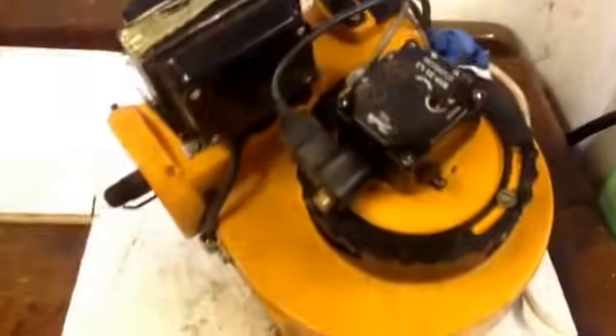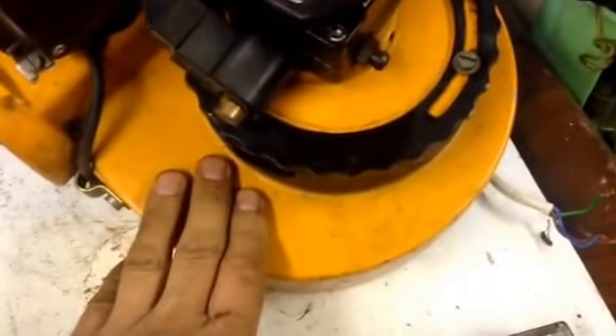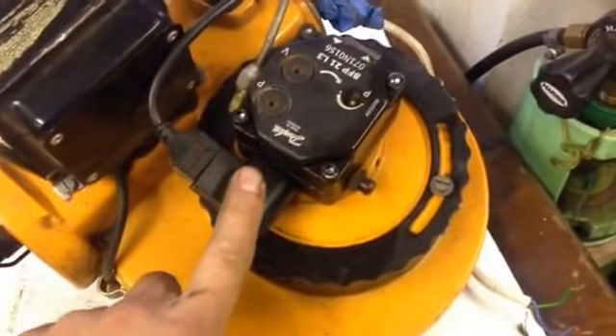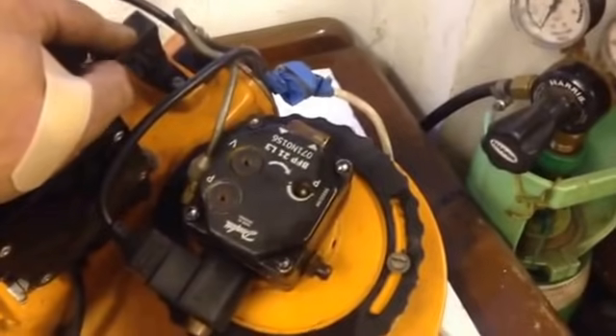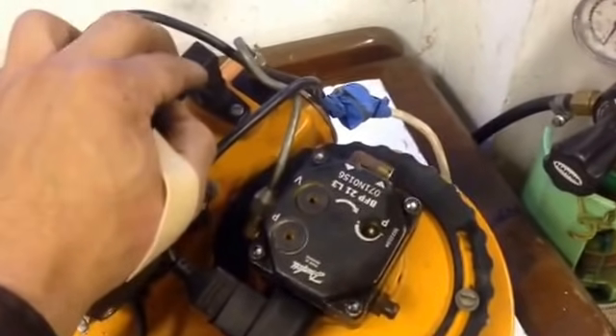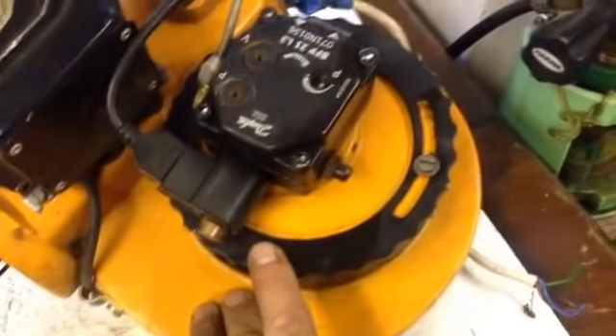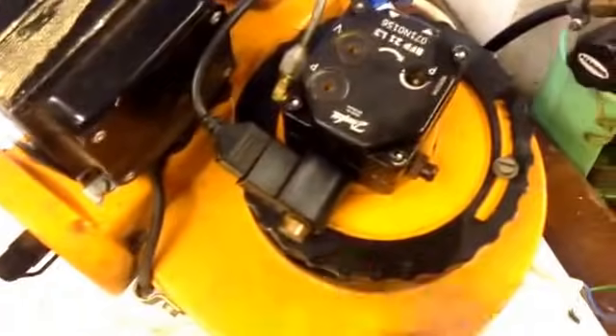Let's look at another common problem. You listen to it run. It has run the fan, it has started to spark, it has clicked as they come on, clicked open the fuel, and it's then ignited. Then the spark has seen the flame, and the spark has stopped. You should be able to hear that. And then it runs for 4, 5, 10, 20 minutes, and then locks out.